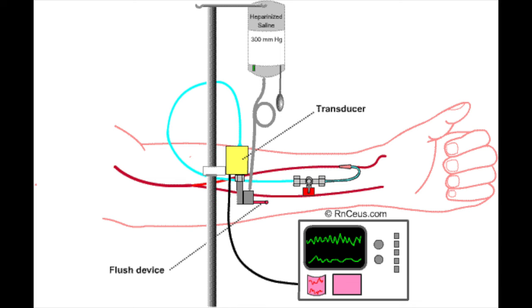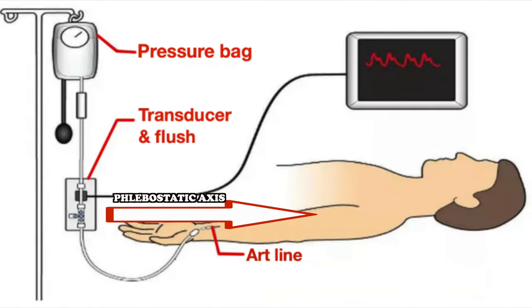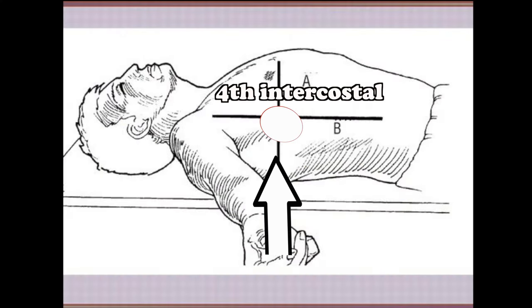Leveling the transducer: The transducer air reference stopcock should be at the level with the phlebostatic axis reference point. The phlebostatic axis reference point is at the fourth intercostal space at the mid anterior posterior diameter of the chest wall.